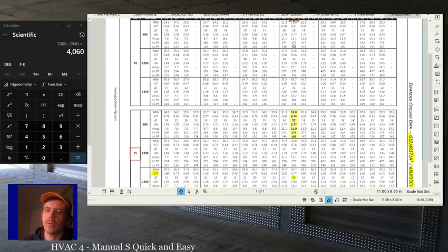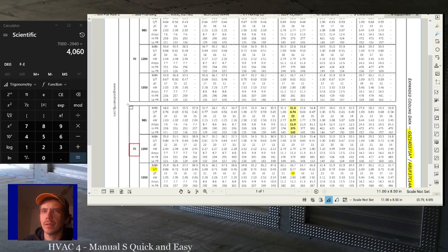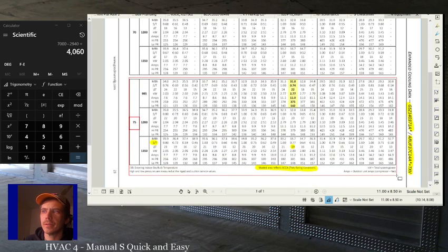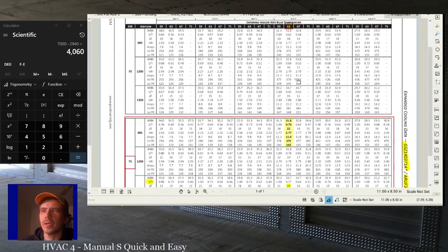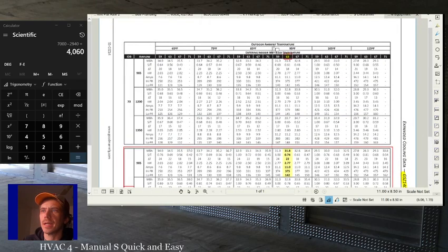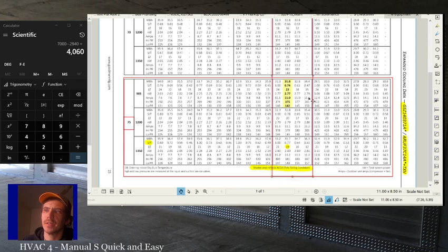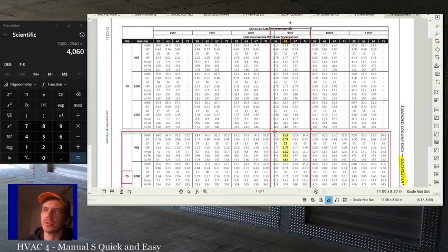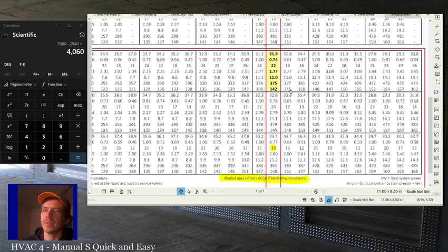Alright, so now we know we're in this set of rows, right? And we are in this set of columns if our outdoor design temperature is 95. If you have a different outdoor design temperature, you should be in these other columns, right? But in general, especially Virginia, you're going to be at 95 degrees, so you're at this set of columns, right? And really, we can narrow that set of columns down to this 63 degree wet bulb. So now we're right here, right in line with the ACCA design conditions.